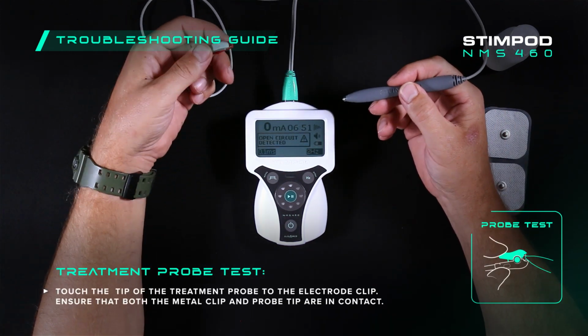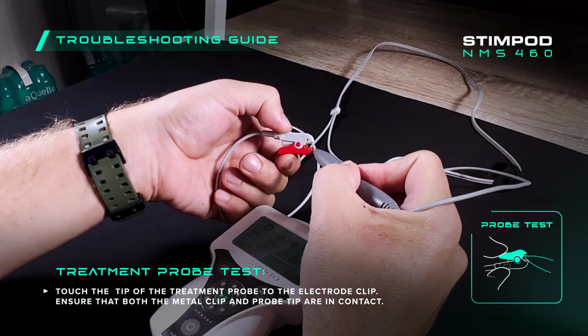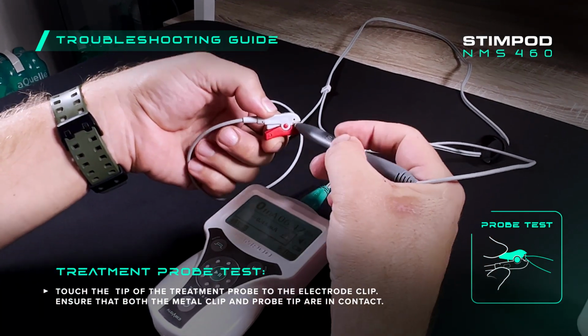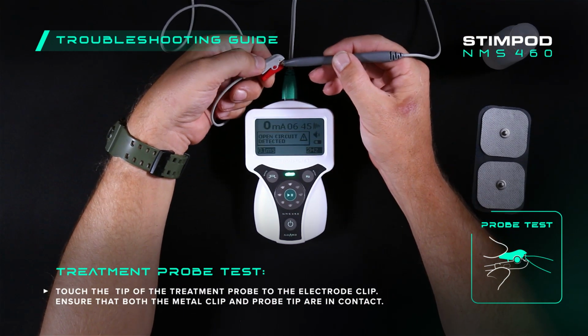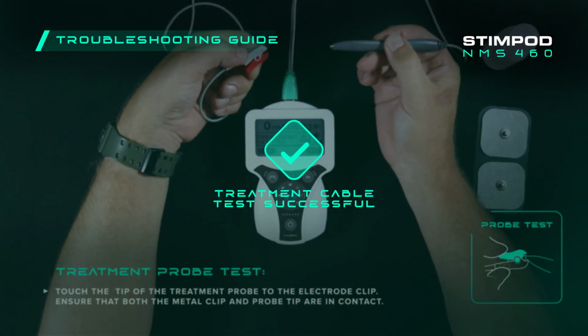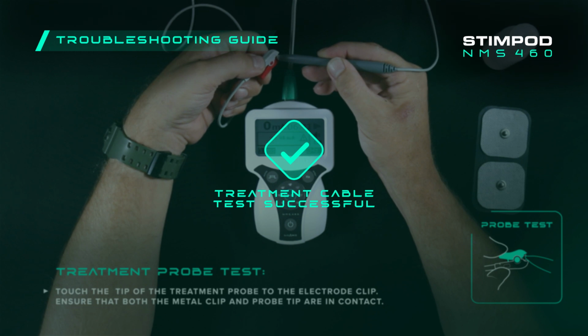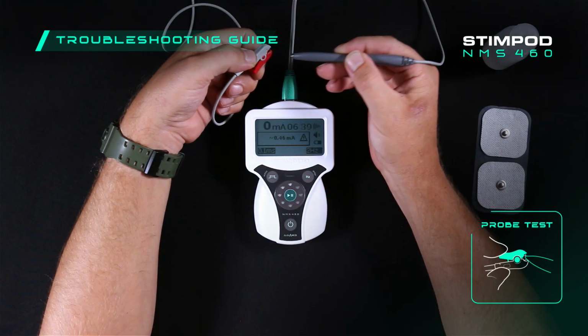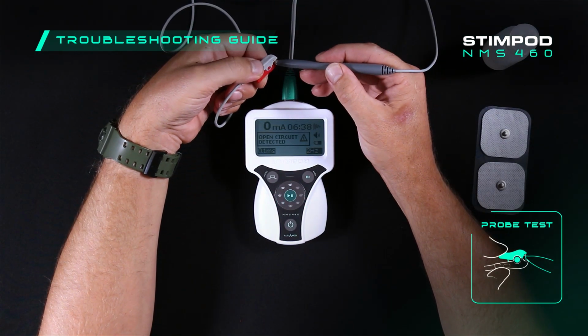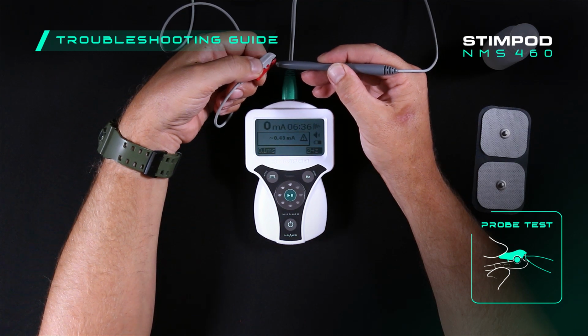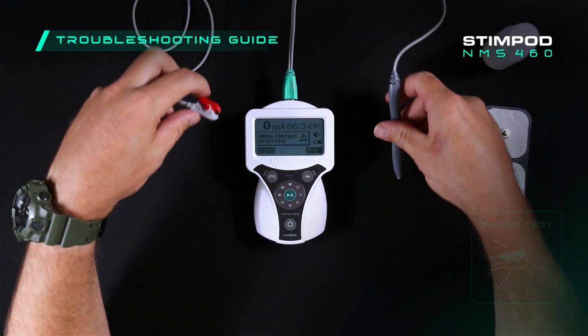If the message is still displayed after replacing the electrode, check if the treatment cable is working correctly. You can test the treatment probe by touching the tip of the probe to the electrode clip, making sure that both metal parts are in contact with each other. If the cable is working correctly, the open circuit message will disappear. If the cable is not working correctly, this means that the stimulation cable may have a fault and will have to be replaced.